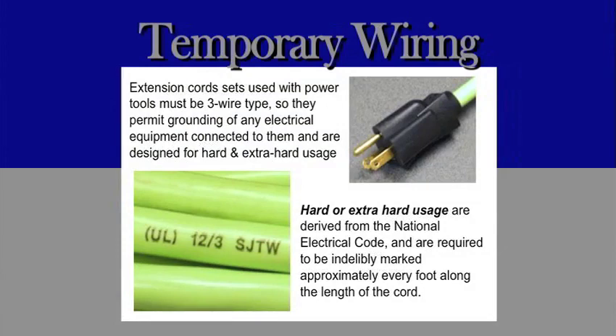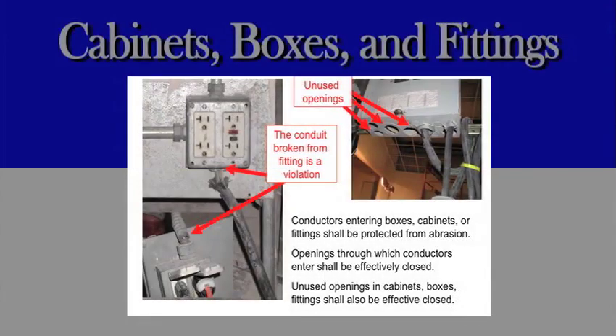Extension cord sets used with power tools must be three-wire type, so they permit grounding of any electrical equipment connected to them, and are designed for hard or extra-hard usage. Hard or extra-hard usage designations are derived from the National Electrical Code and are required to be indelibly marked approximately every foot along the length of the cord. Cabinets, boxes, and fittings. Unused openings, or conduit broken from the fitting, is a violation.